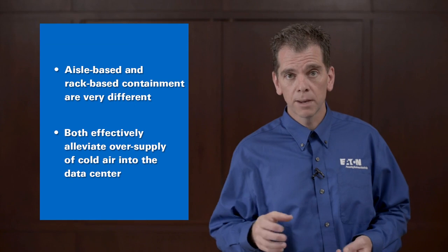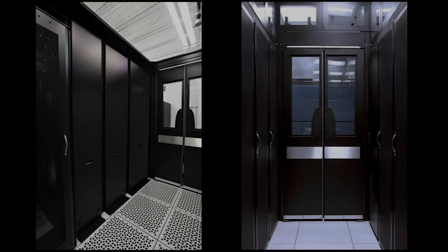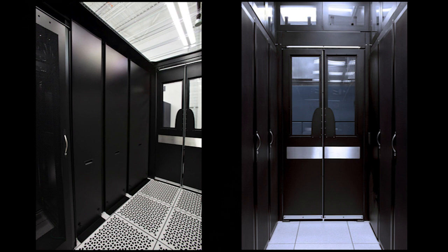You're looking first at big gaping holes, gaps between racks, okay? The ends of the rows themselves. How you address that is simple. Between racks, there's things like vertical partitions or vertical blanking panels that allow you to seal that space off. At the end of the rows, you can add things like end-of-row doors.